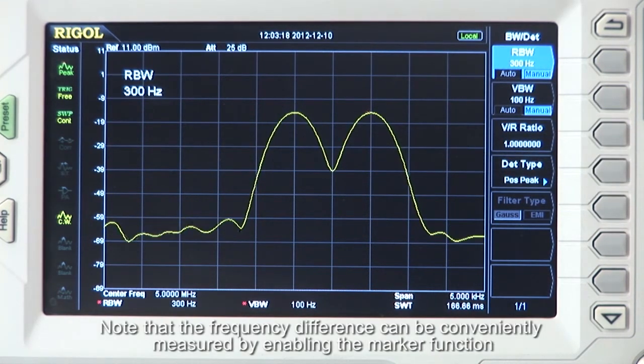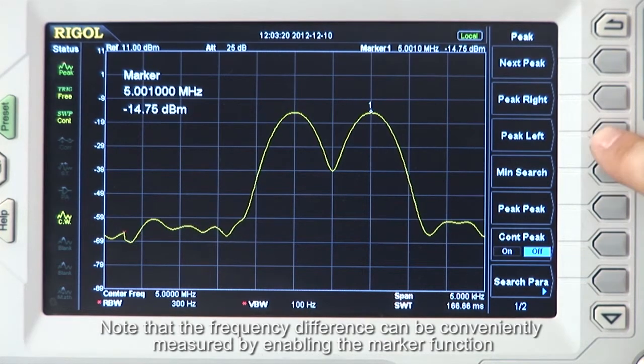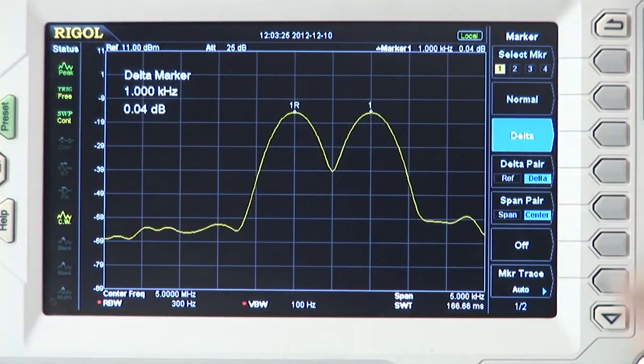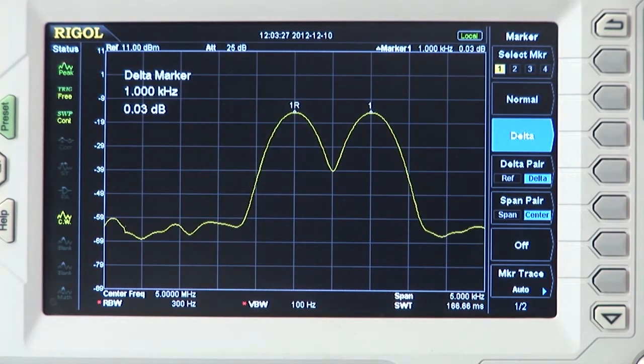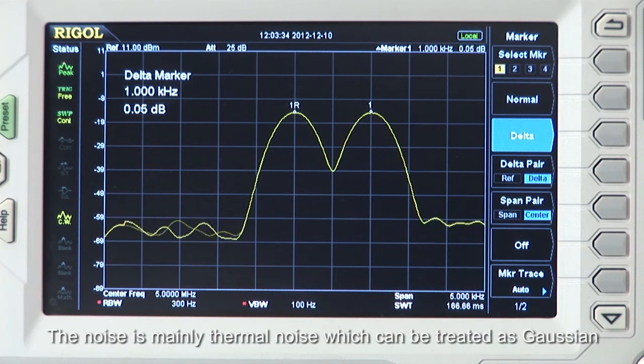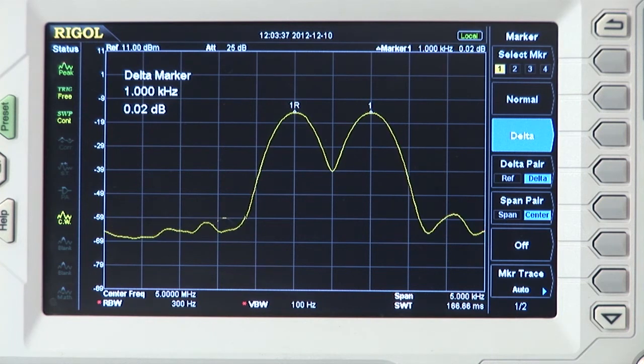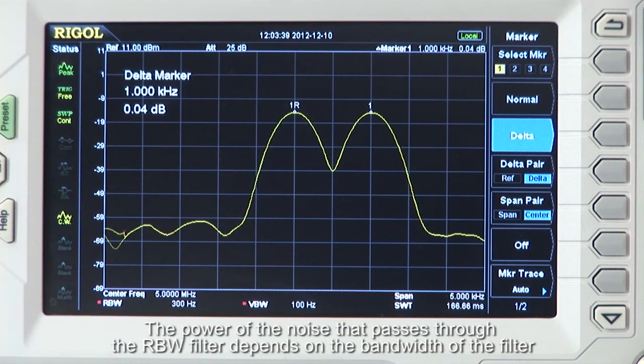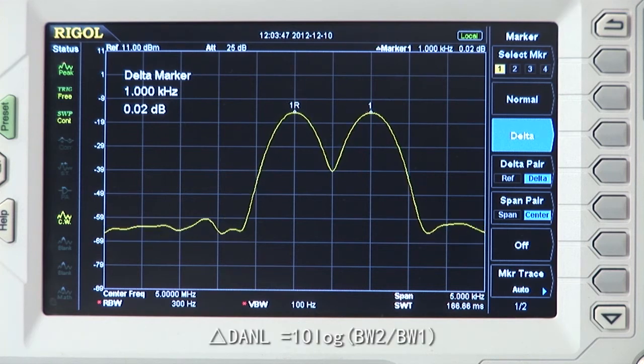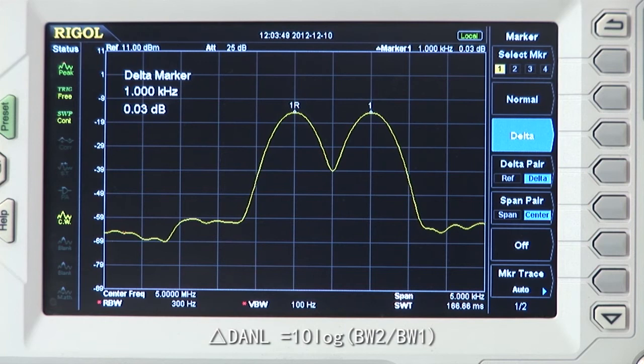Note that the frequency difference can be conveniently measured by enabling the marker function. When you reduce the RBW, it also reduces the displayed average noise level of the analyzer. The noise is mainly thermal, which can be treated as Gaussian. The power of the noise that passes through the RBW filter depends on the bandwidth setting of the filter. The relationship between the noise level and RBW bandwidth is: delta DANL equals 10 log (bandwidth 2 divided by bandwidth 1).